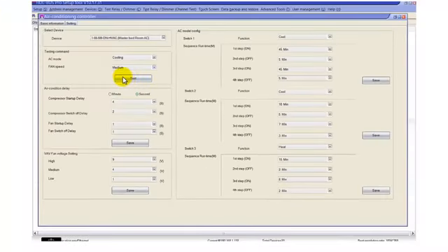When you press test, it will send the command to your HVAC module to run the AC in cool and the fan on medium. We always do this just as a test to make sure that your wiring is correct with the HVAC engineers or the commissioning person. You always make sure to give him all the speeds, medium, high and low, to double check your connection is done properly.